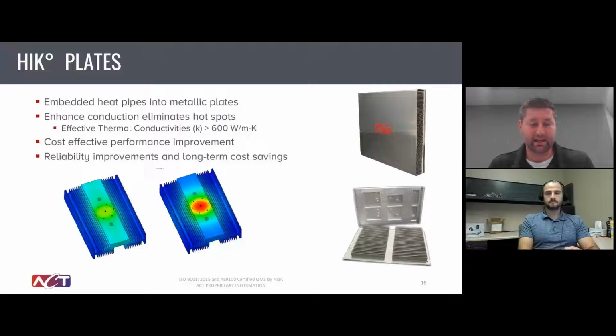Now we'll look at that exact example. In many cases in the power electronics world, the goal is to eliminate hotspots. One area we've explored a lot is embedding heat pipes into metallic plates, in most cases aluminum, because it's fairly cost effective and already has good thermal properties. By embedding heat pipes into aluminum plates, you can increase the thermal conductivity by a couple of factors. Aluminum is typically between 150 and 200 watts per meter K. By implementing heat pipes, you can easily achieve 600 watts per meter K, and in certain cases with long distance heat transfer, you could exceed 1,000 watts per meter K.